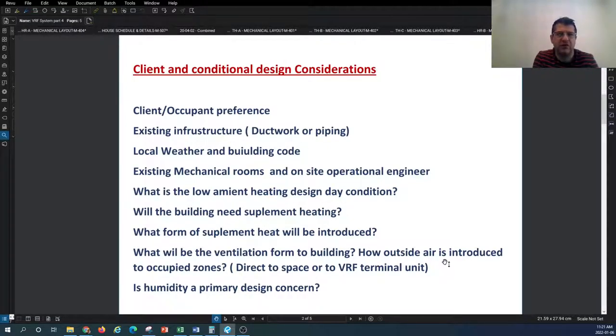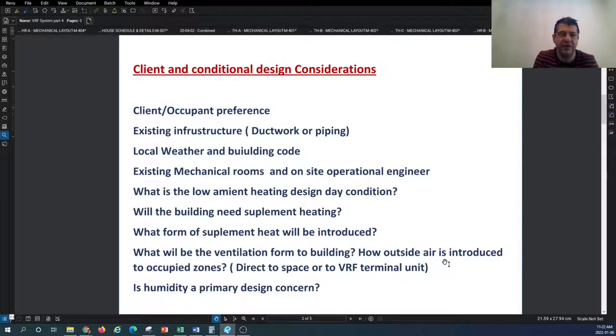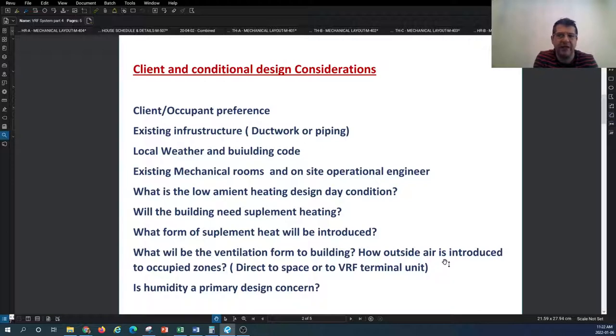Other considerations include your local weather and building code conditions. Local weather tells you about your ultimate cooling and heating degree days and gives you an idea of whether a VRF system is efficient for your geographical area. Also, local building codes may have requirements around control of refrigerant and the volume of refrigerant in the building that you need to be concerned about from a code perspective in your jurisdictional area.